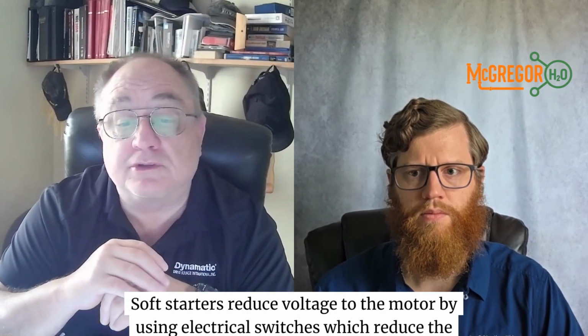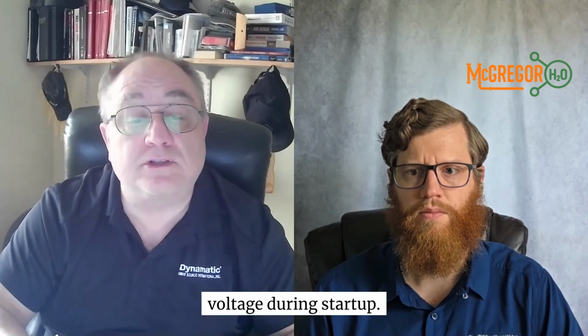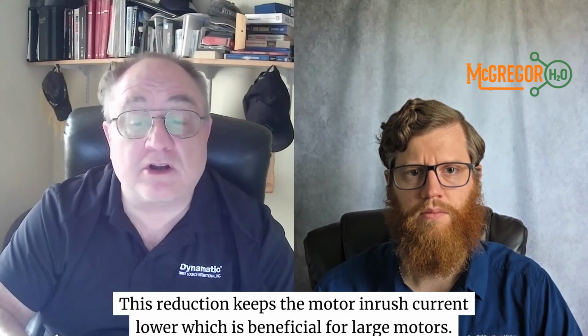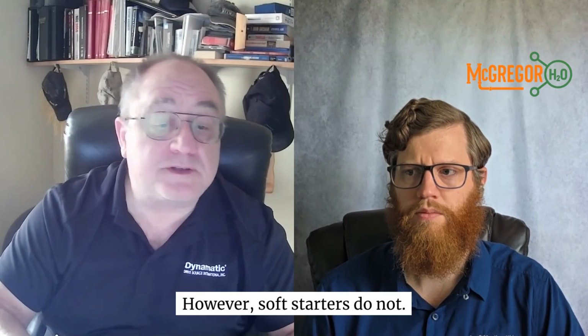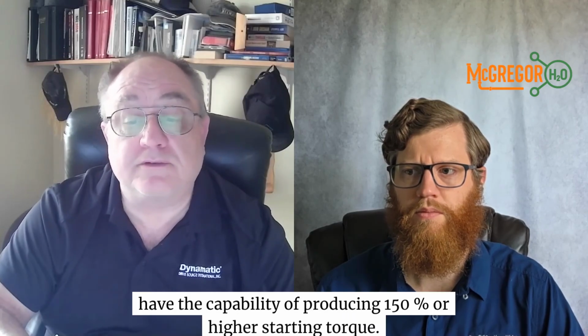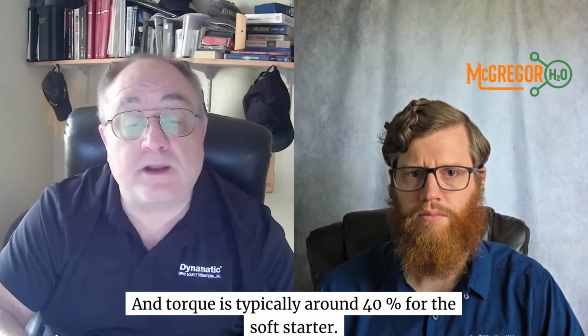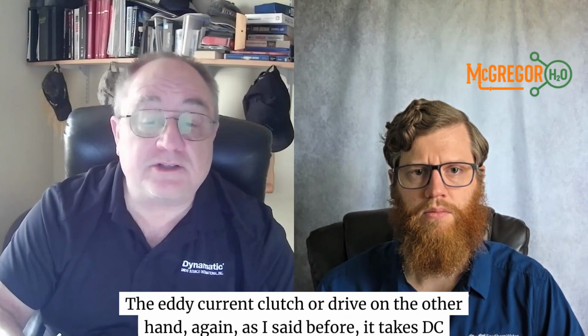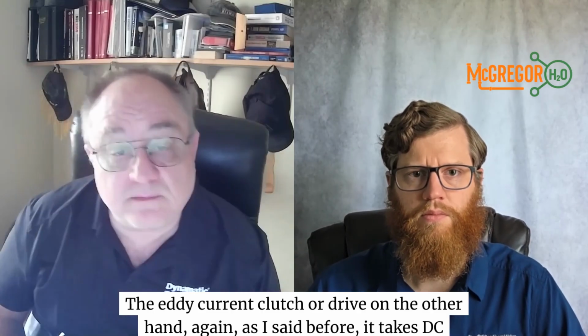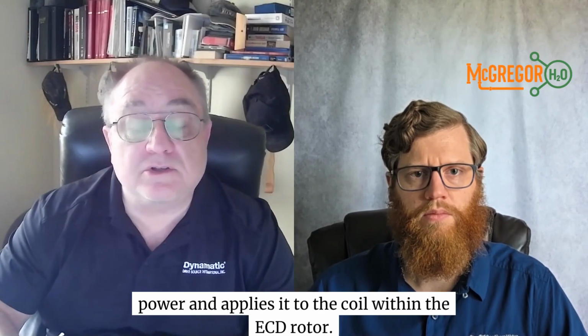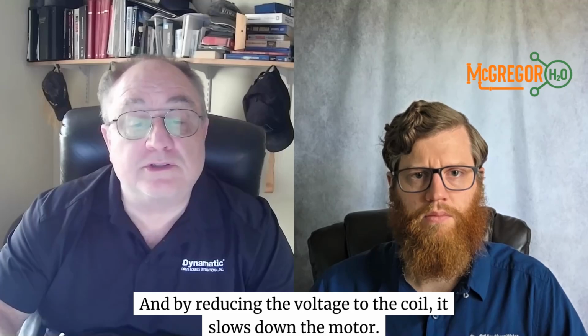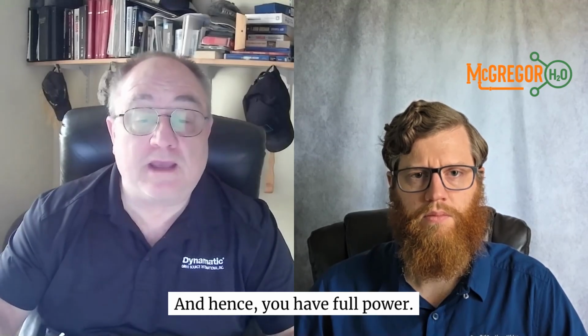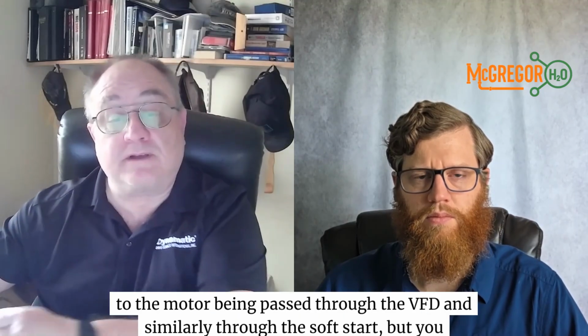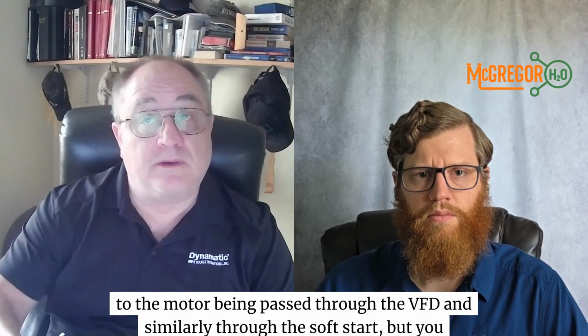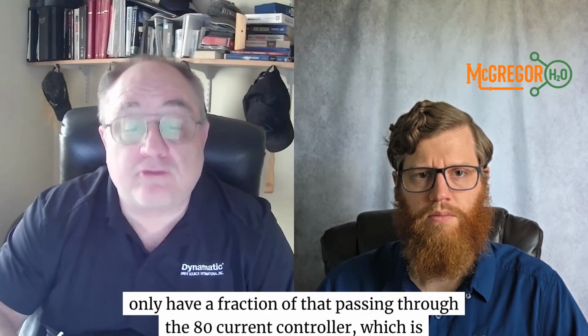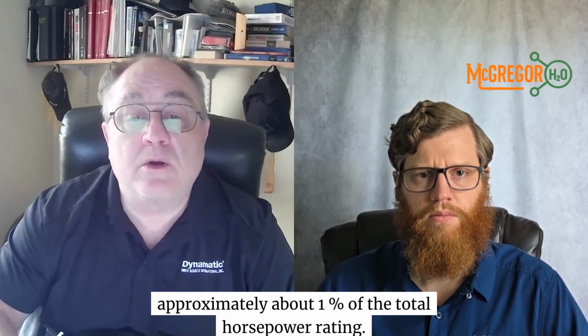Soft starters reduce voltage to the motor by using electrical switches, which reduce the voltage during startup. This reduction keeps the motor inrush current lower, which is beneficial for large motors. However, soft starters do not have the capability of producing 150% or higher starting torque, and torque is typically around 40% for the soft starter. The eddy current clutch or drive, on the other hand, as I said before, takes DC power and applies it to the coil within the ECD rotor. And by reducing the voltage to the coil, it slows down the motor. Full power to the motor is passed through the VFD and similarly through the soft starter, but you only have a fraction of that passing through the eddy current controller, which is approximately 1% of the total horsepower rating.